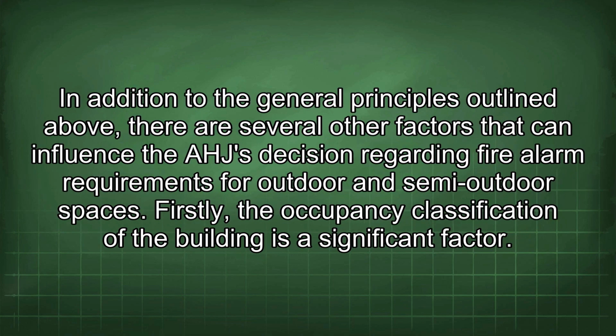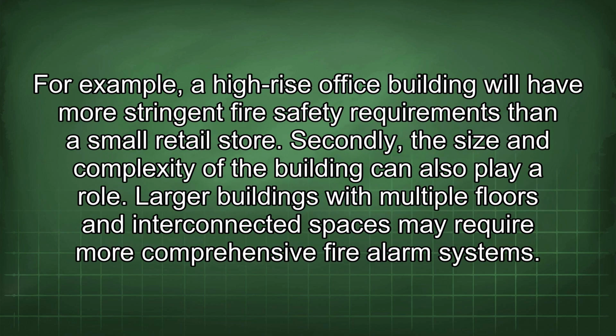system. In addition to the general principles outlined above, there are several other factors that can influence the AHJ decision regarding fire alarm requirements for outdoor and semi-outdoor spaces. Firstly, the occupancy classification of the building is a significant factor. For example, a high-rise office building will have more stringent fire safety requirements than a small retail store. Secondly, the size and complexity of the building can also play a role. Larger buildings with multiple floors and interconnected spaces may require more comprehensive fire alarm systems.